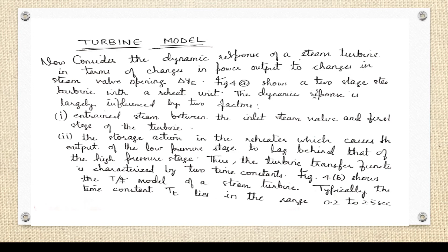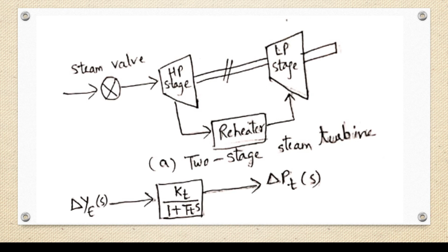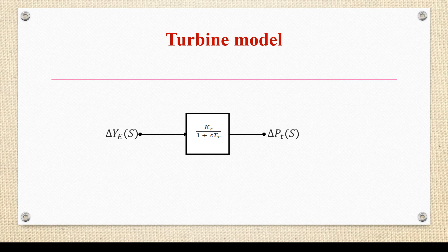This figure shows a two-stage steam turbine with a reheat unit. The dynamic response is largely influenced by two factors here. First, entrained steam between the inlet steam valve and the first stage of the turbine, and second, the storage action in the reheater, which will cause the output of the low pressure stage to lag behind that of the high pressure stage. Thus, the turbine transfer function is characterized by two time constants, and the second figure shows the transfer function model of a steam turbine. The time constant Tt lies in the range 0.2 to 2.5 seconds. So this is the block diagram showing the transfer function model of a steam turbine, delta Pt of s equals Kt by 1 plus s Tt into delta Ye of s.